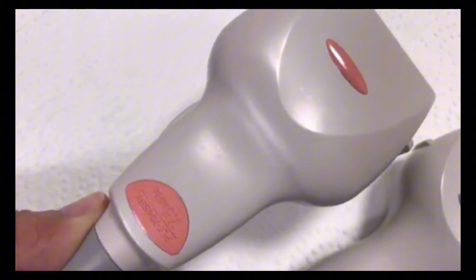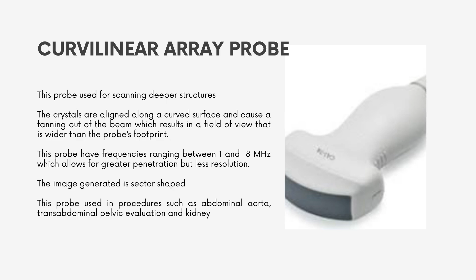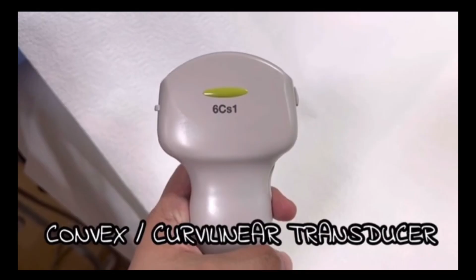Curvilinear array probe. This probe is used for scanning deeper structures. The crystals are aligned along a curved surface and cause a fanning out of the beam, which results in a field of view that is wider than the probe footprint. These probes have frequencies ranging between 1 and 8 MHz, which allow for greater penetration but less resolution. The image generated is sector shaped. This probe is used in procedures such as abdominal, transabdominal, pelvic evaluation, and kidney.